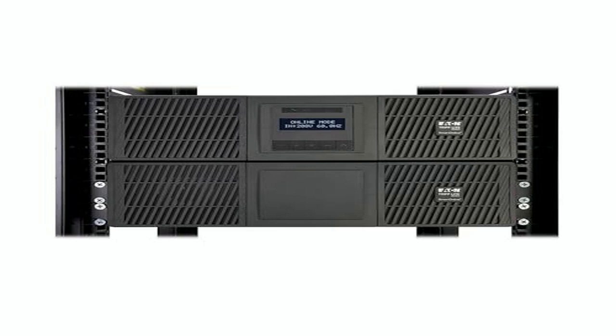What that means in practice is you can plug in standard 120V equipment, servers, networking switches, even a few desktop workstations directly into the unit without needing a separate transformer box. For a rack that's already populated with 208V equipment, you get the flexibility to add a mixed set of devices without rewiring the whole cabinet.